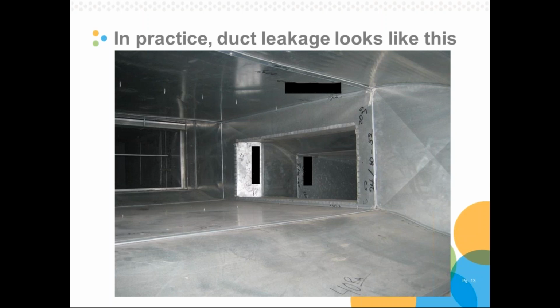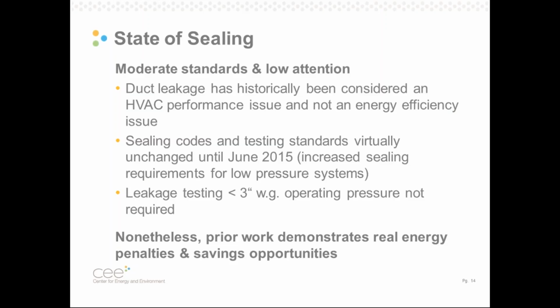And it's all these seams and joints between the different components of the duct system that add up to give us the duct leakage we measure and the duct leakage that causes energy penalties. So I'll pause here briefly to say that there's a lot more in our report about the state of sealing with respect to codes and with respect to the attitudes on duct sealing and duct leakage from field personnel, including code officials, sheet metal workers, TAB contractors, etc., and design engineers.